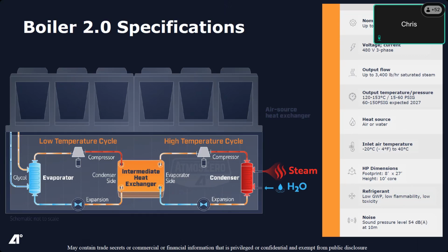the customers may be. If you look at the right side of the screen there, that is the condenser and the heat sink side. So we're taking feed water in, the exact same feed water that you typically have in a boiler room today. So anything you're making steam with today will work fine for these condensers from a water quality standpoint. The steam that comes out is either 60 psi or less right out of the heat pump. So for building stock, that works fine.